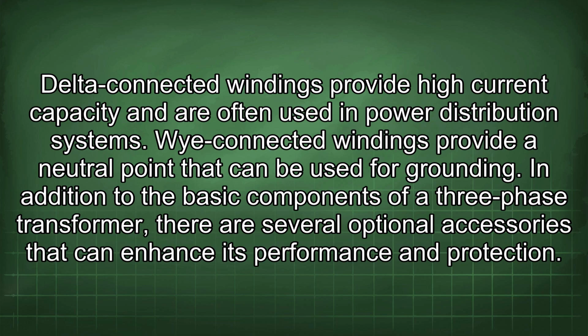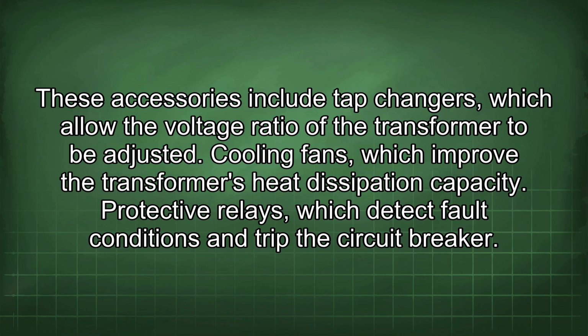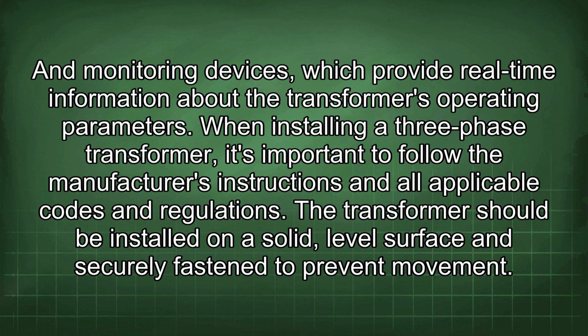In addition to the basic components of a three-phase transformer, there are several optional accessories that can enhance its performance and protection. These accessories include tap changers, which allow the voltage ratio of the transformer to be adjusted, cooling fans, which improve the transformer's heat dissipation capacity, protective relays, which detect fault conditions and trip the circuit breaker, and monitoring devices, which provide real-time information about the transformer's operating parameters.